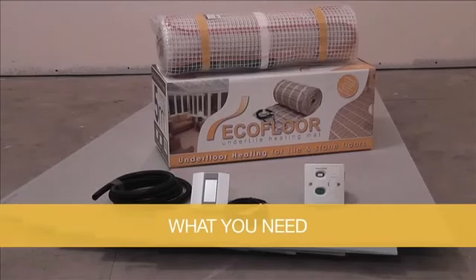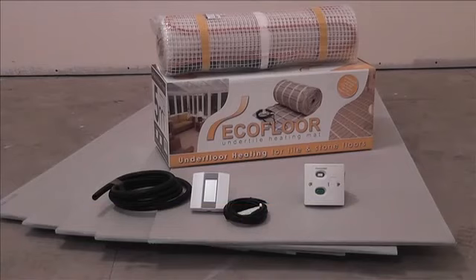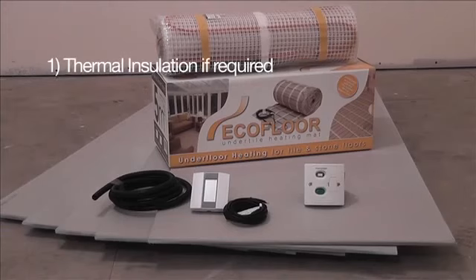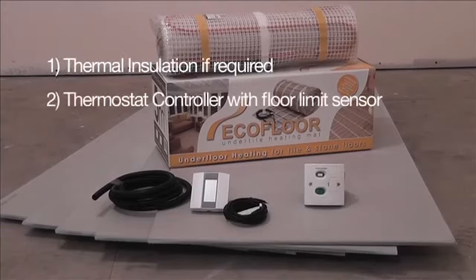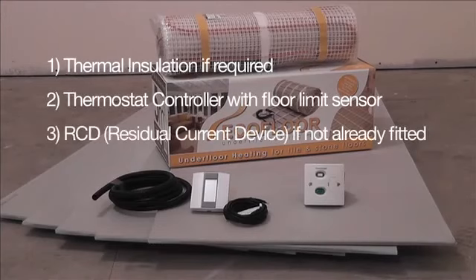to help. The ECOFLOOR heating mat is a heating cable pre-attached to a self-adhesive mesh. The mat design enables fast installation and an even heat distribution across the floor. You will require the following accessories to install the heating system: the thermal insulation if required, the thermostat controller with floor limit sensor, and an RCD if not already fitted.